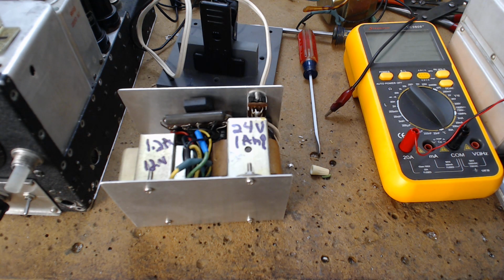Now if you go reverse with that kind of transformer, the shit's going to hit the fan, you're going to have losses. Even when the transformer is just hooked to the other one running, nothing on the output of the second transformer, I was measuring 500 milliamps loss, half an amp. I was like, what the hell's going on? Why do I always find these things?